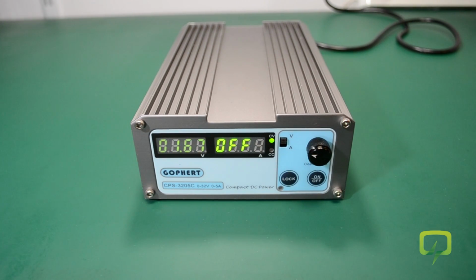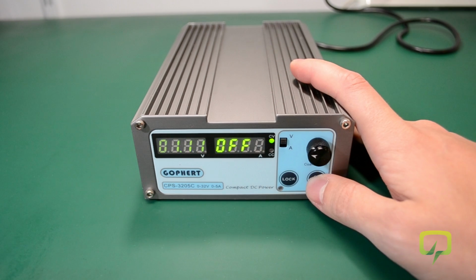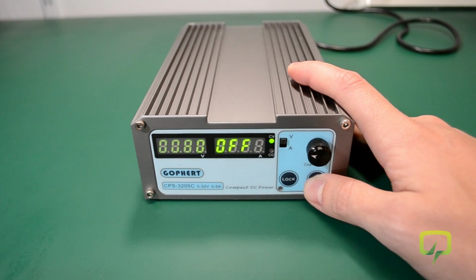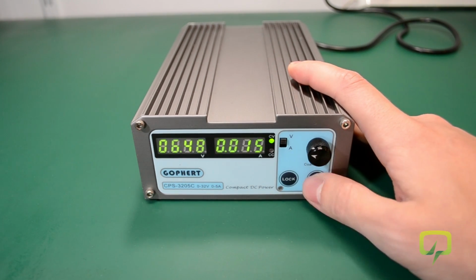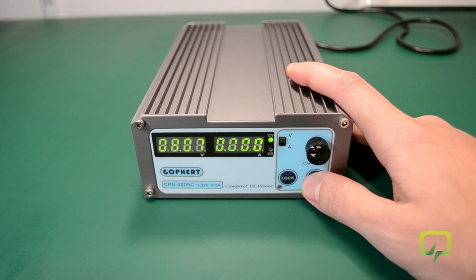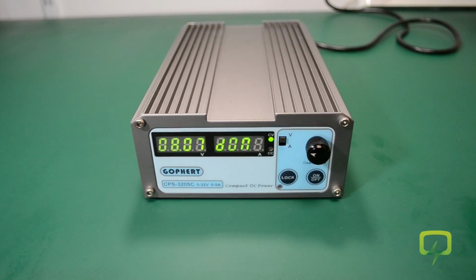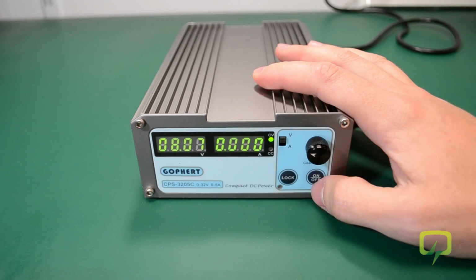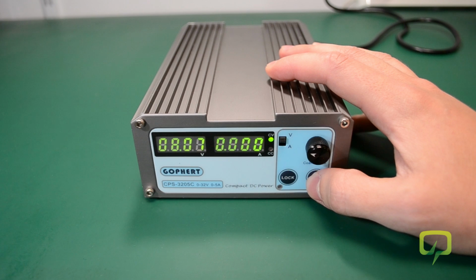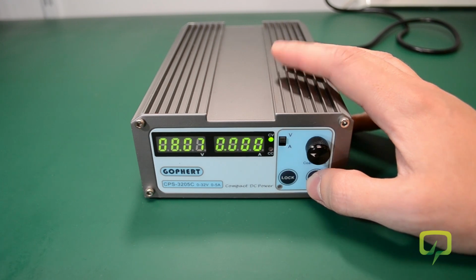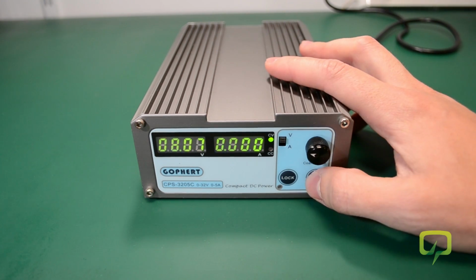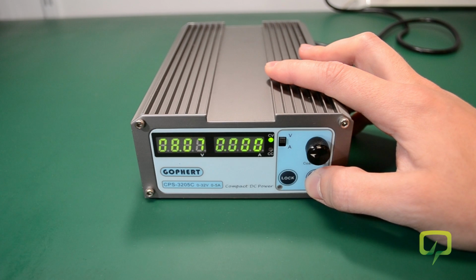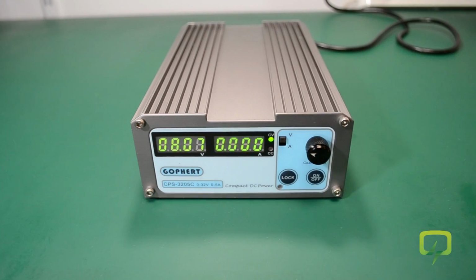If you press this button for 5 seconds, it will display D on or D off, and that's how you control the behavior of the power supply at power on. If D on was displayed, it means you've automatically enabled the output of the power supply at power on, or if you set it to D off, it means the power supply will come on with its output off.